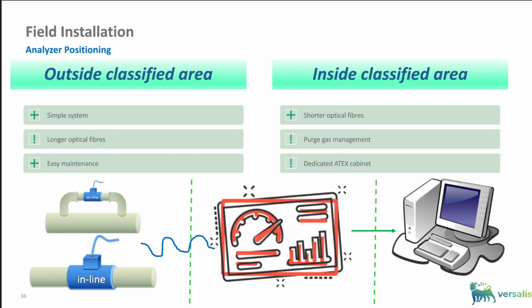The other aspect is the positioning of the analyzer. It may be outside the classified area, in the safety area, which is the simple solution, but may involve a distance too great to be covered by optical fiber. In such a case, an ATEX cabinet must be provided to house the analyzer in the hazardous area.